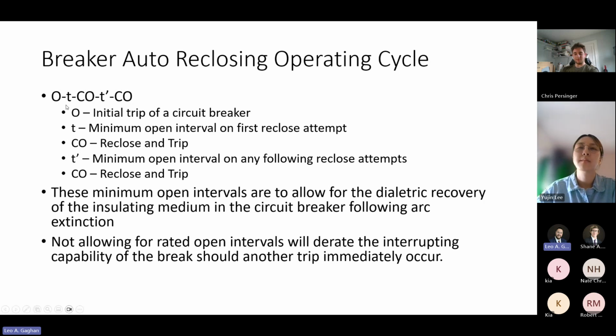So the T, right, just the regular T, that tends to be a little bit of a shorter time duration because this breaker's been sitting there. It's got stored energy that it can use. Right, it trips. When it goes to reclose, it's got that stored energy just ready to go. But it uses it. If you retrip again, well, now it needs to take time, build that energy back up, charge, and then it needs to have that time before it can reclose again. So that's why you have different times for that initial reclose versus following recloses. They give it that charging time, as it says right here, pretty much.